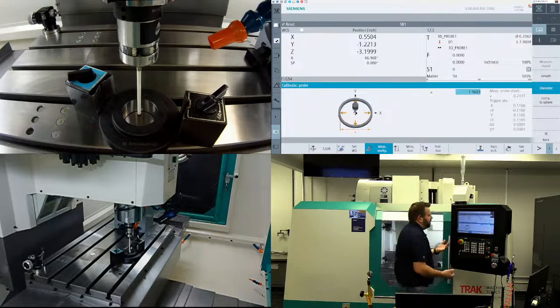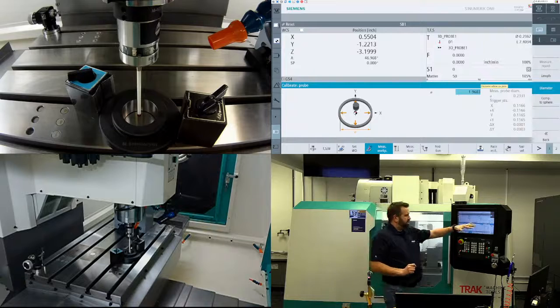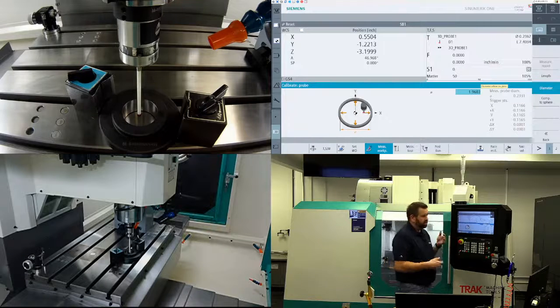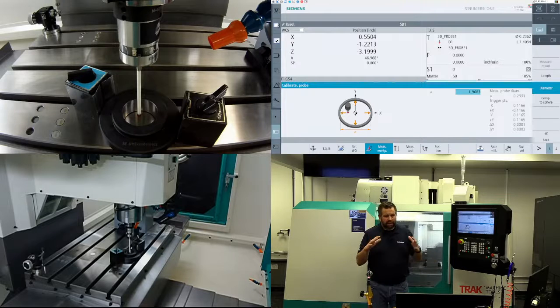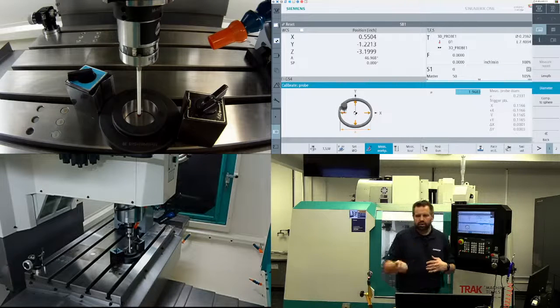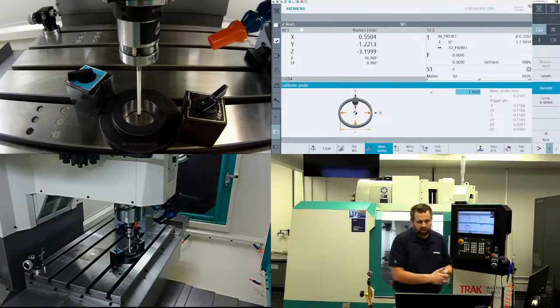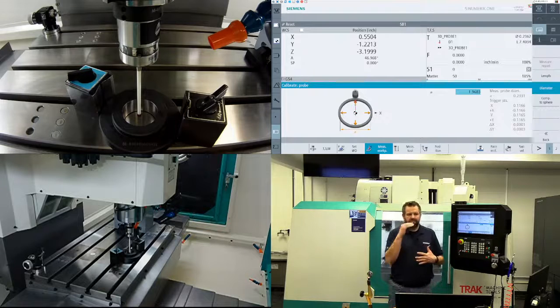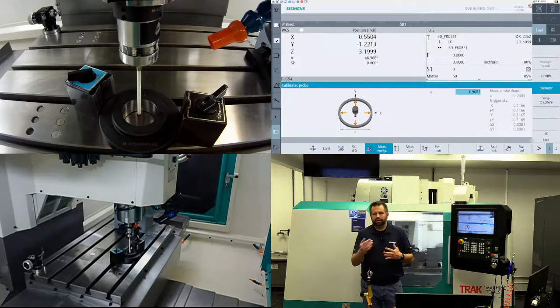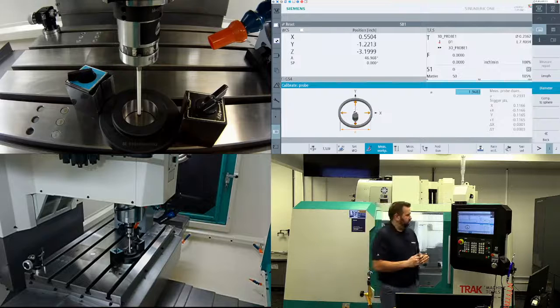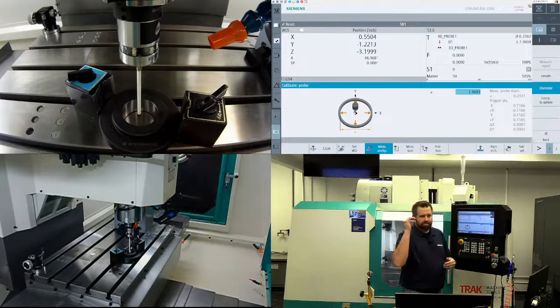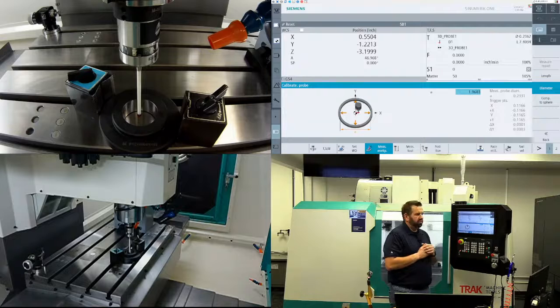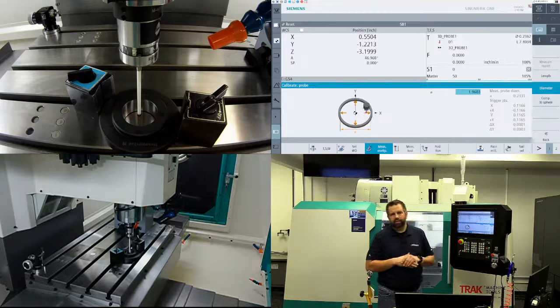So we go to the diameter screen now, and now we have a field that we enter in that value. So this value is important, right? If you're ever out there and you cannot enter in that value, let's say you go to your machine and it won't let you enter this value, there's an MD. I specify that MD in the document that you can download in the description. The ability here is setting it to -1. Now you have the ability to put in the diameter of whatever ring gauge you have, okay?